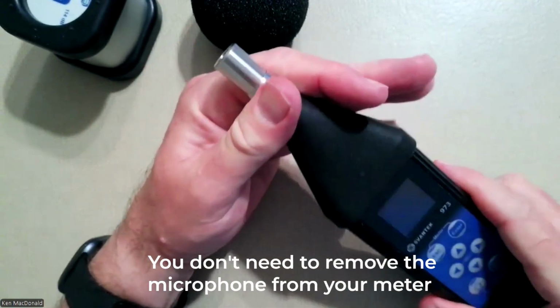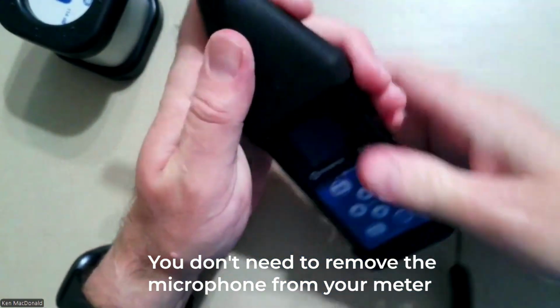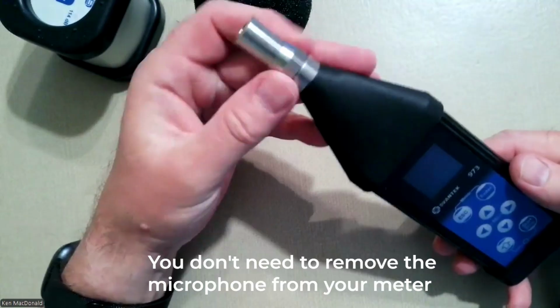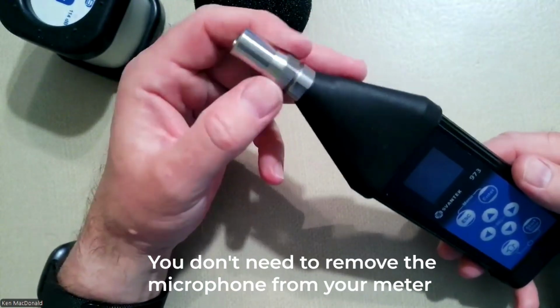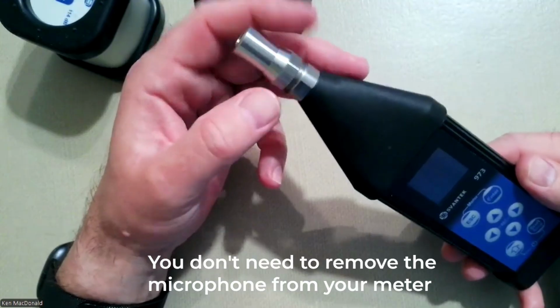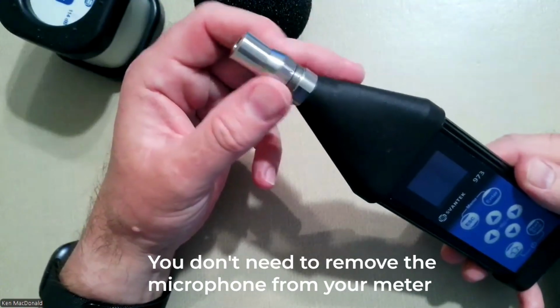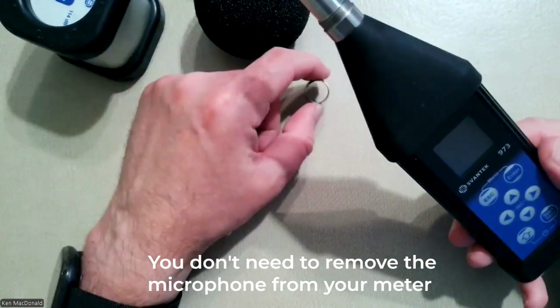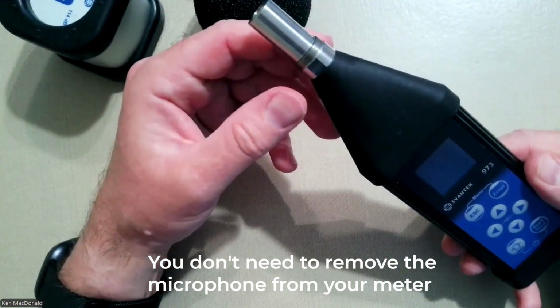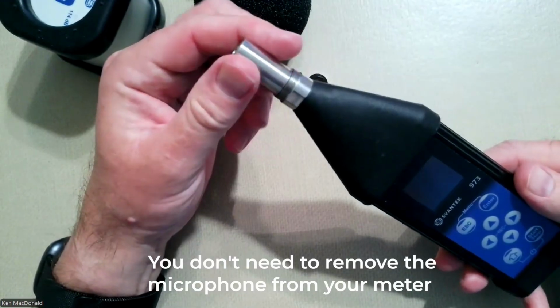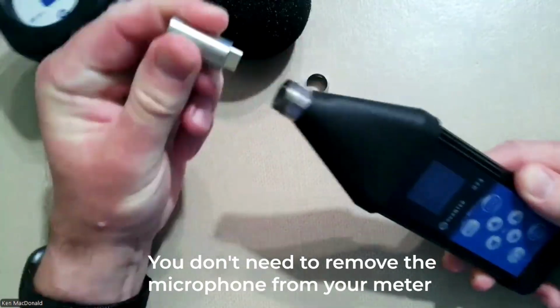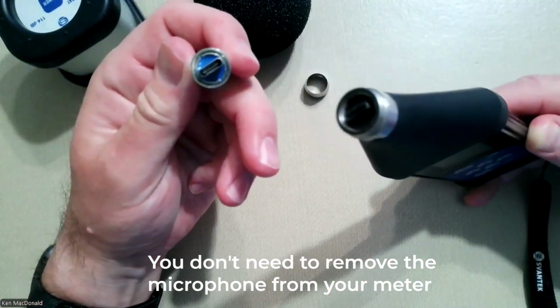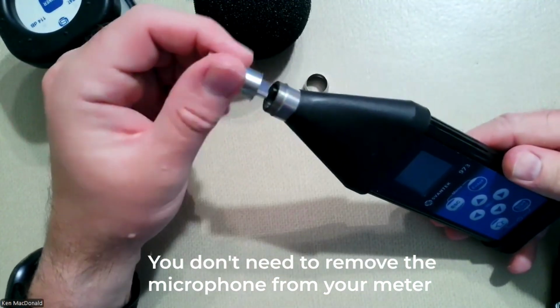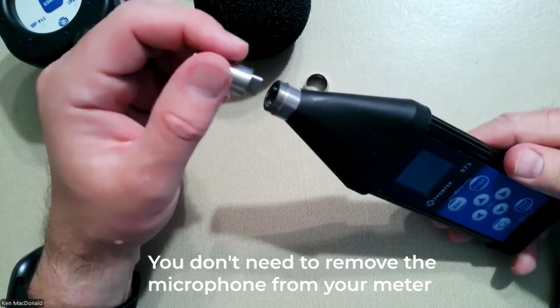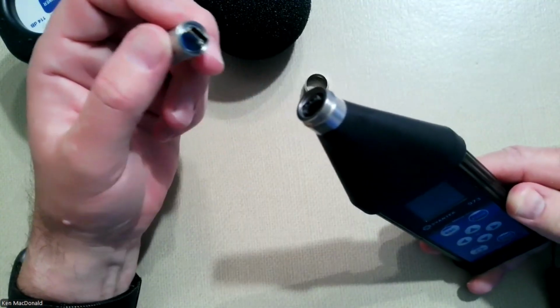And I wouldn't recommend this, I'm just going to show you. I'm going to loosen up this retaining nut, and I'll remove this. You should never really need to do this. The microphone is a MEMS microphone. It basically is a version of the microphone that's in your cell phone, but a way better version with very good specifications. But also, like your cell phone microphone, it is very rugged. But the reason we don't want to rotate this is that this is a connection into the meter. So if I was to put this in and rotate it, I may risk damaging the connector here. And on different meters, it's slightly different. But basically, this is why.